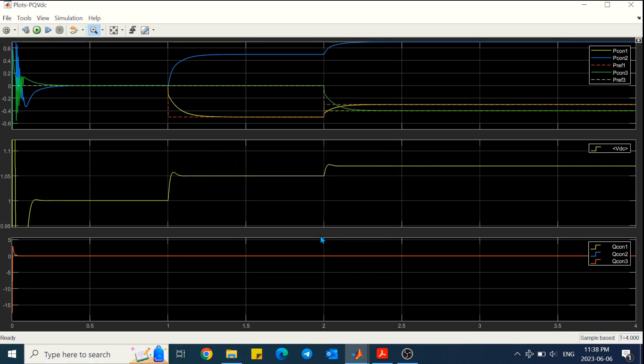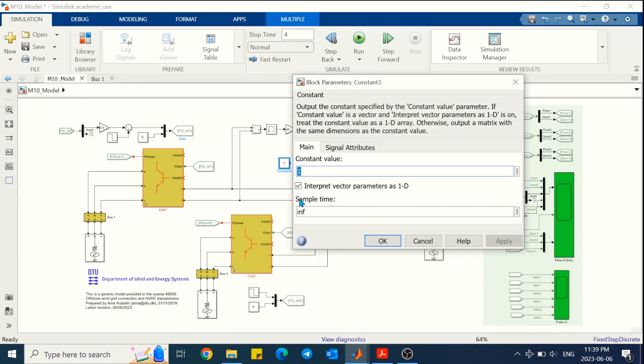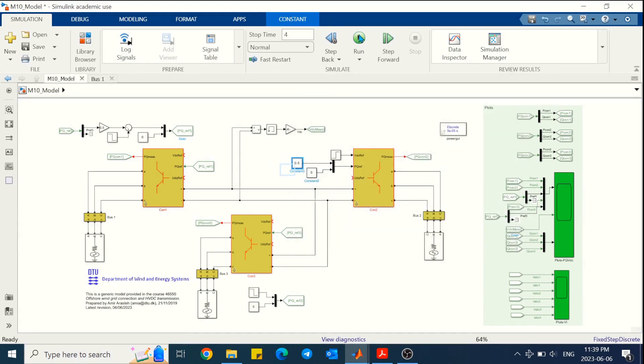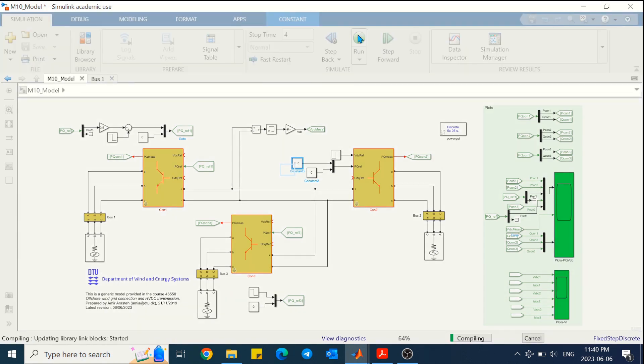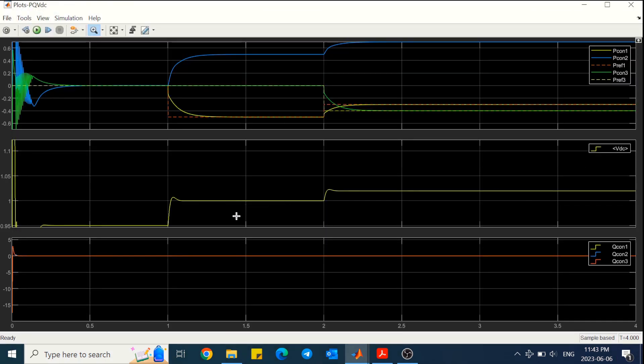Let's assume that this 0.5 per unit of active power is our default value for power flow in this system, and we don't want to experience any deviation in DC link when 0.5 per unit of active power is flowing from converter 1 to converter 2. For that we need to provide this value for the reference of converter 2 as well, so now the reference value of converter 2 is always 0.5 per unit. If we look at the signals, when the active power of converter 2 is 0.5 per unit, we don't see any deviation in DC link voltage because there is no mismatch between reference and measured value of power. When there is no power flow at the beginning we see a voltage drop on DC link, and when power of converter 2 is larger than 0.5 we see the steady state DC link voltage is increased.